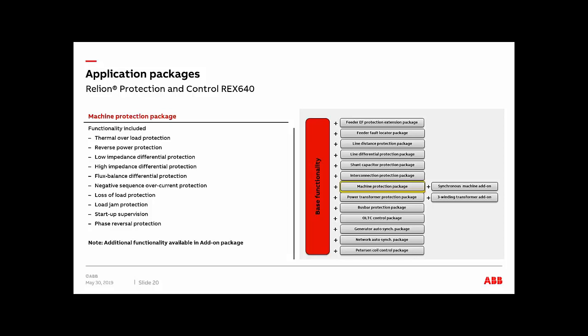There is your negative sequence overcurrent protection, the loss of load protection or undercurrent protection 37, and load jam protection, that's also available. You get a startup supervision, and it's pretty much going to prevent you from starting your machine too many times, excessive startups. That's also available there. And your phase reversal, which just prevents problems if you have a reverse connection in one of the phases. You will monitor the negative sequence in your machine and prevent overheating and failure with this protection.